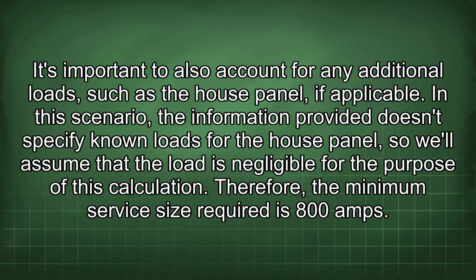It's important to also account for any additional loads, such as the house panel, if applicable. In this scenario, the information provided doesn't specify known loads for the house panel, so we'll assume that the load is negligible for the purpose of this calculation. Therefore, the minimum service size required is 800 amps.